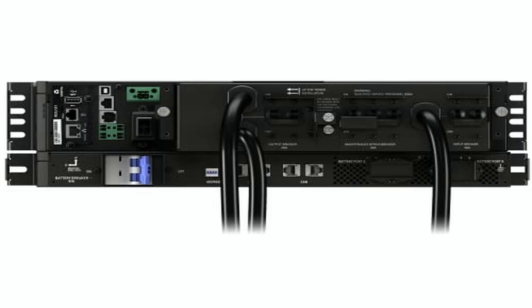On the flip side, skip this one if your load is under 1 kilowatt, you're protecting just a few peripheral devices, or you have a tight capex budget with no plan for future expansion. In those scenarios, a smaller line interactive UPS or even a UPS-as-a-service subscription might give you the same protection without the rack footprint and the need for professional installation. Also, if you're in a region where the electrical code restricts the use of lithium-ion UPS systems in certain facilities, you'll need to double-check compliance before you order.